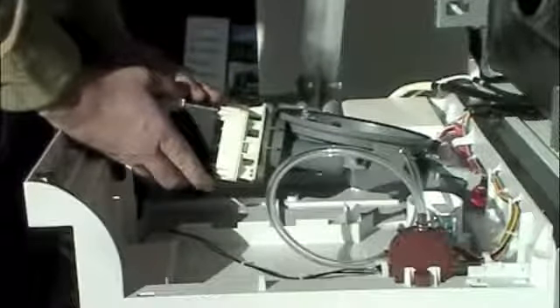If that fails and that part is clean and we know that everything else is in line, then we can start looking at the main motor and the relay assembly. And so here it is in all its glory. Basically this motor here is easily removed. I'm going to talk a little bit about testing and then I'll show you how it comes out. You need to check your continuity on this motor. Check each winding. Make sure we don't have any opens or shorts, and that it's not grounding somewhere it shouldn't.